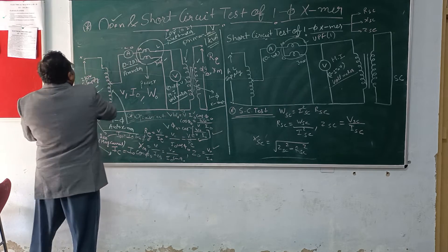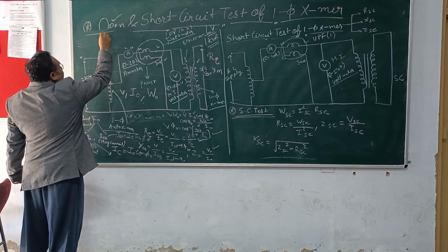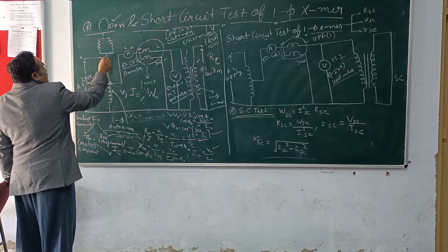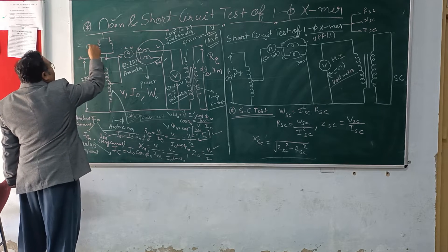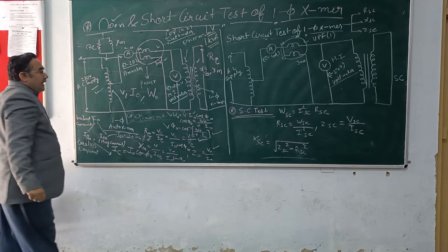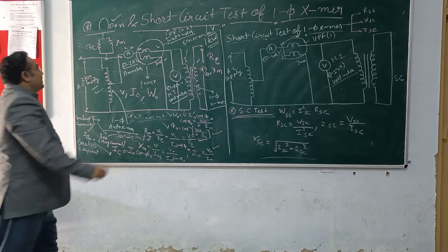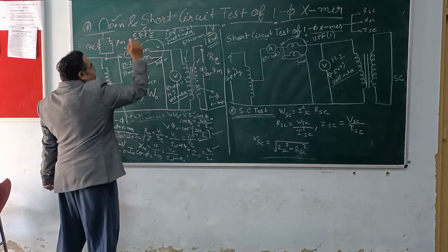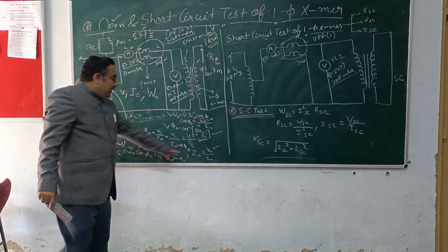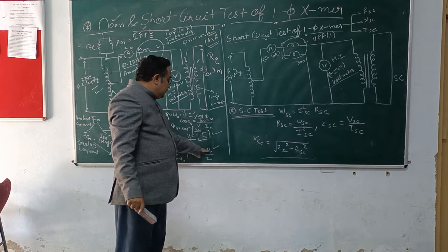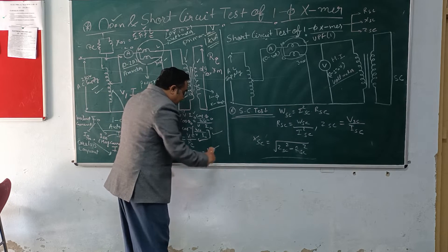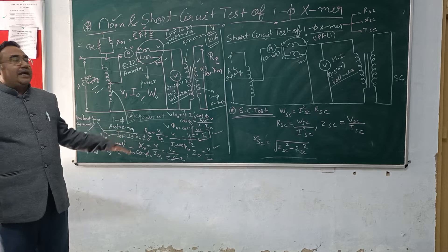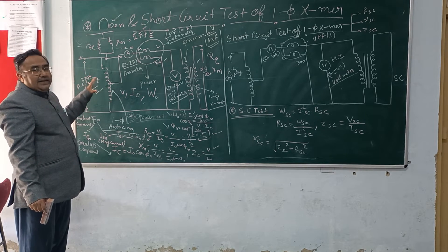You can also calculate the inductance L, because XM is nothing but 2πFL, where F is 50 hertz. So you can calculate L as well. Similarly, the no-load impedance can be calculated as V0 upon I0. So all the parameters related to the transformer at no-load can be calculated with the help of this open circuit test.